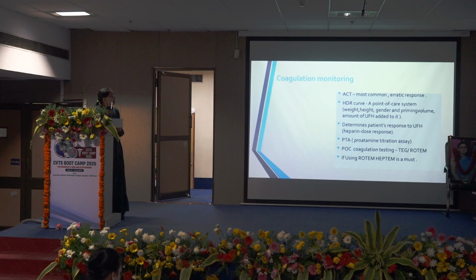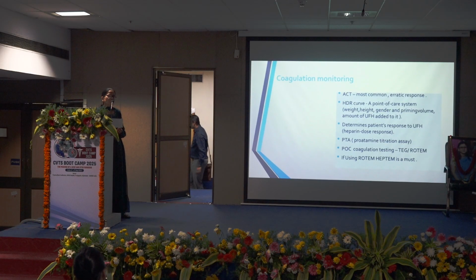So there are many point of care systems which will monitor the heparin dose response curve for that patient. That will depend upon the weight, height and gender of the patient, how much priming volume has been added to the pump, and how much unfractionated heparin the perfusionist has added to the pump. All of those it will take, and at 3-4 points they will calculate and plot a curve. From that we can calculate that patient's response to the heparin. That is known as the heparin dose response curve.